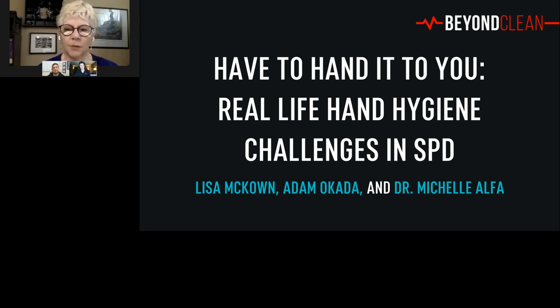In terms of the guidelines, I know the CSA document talks about the fact that if instruments go through a washer disinfector and are exposed to 90 degree temperatures, that thermal decontamination is thought to be enough to make those instruments safe to handle without gloves. So we wear gloves on the reprocessing or cleaning side because those instruments have organic material - they could have viruses, bacteria, etc. To protect the reprocessing staff, absolutely you wear gloves there, and nobody would think differently. On the clean side, if instruments have gone through a washer disinfector and been thermally decontaminated, the dogma has always been that it makes them safe to handle - so it's okay to handle them with your hands.